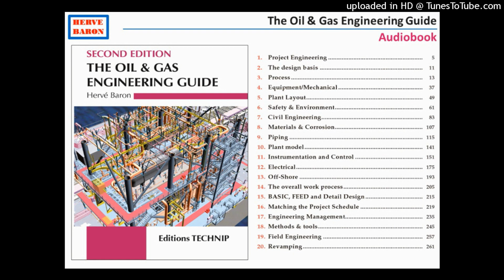The open drain network also collects small oil spills that could happen around equipment and are collected in equipment drip pans. The open drain network also connects with the rainwater collection system in the paved process area. The open drain system leads to the wastewater treatment plant, where oil is separated from water and water can be disposed of outside the plant.